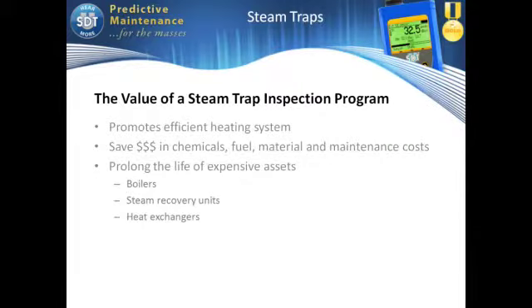You need to think about promoting an efficient heat system in the steam system. This is what it's about. We're trying to increase the efficiency of your heating system. I've been in situations where there have been so many problems with steam traps, so much air, so much condensate in the system, that they've not been able to achieve a certain temperature. Without this temperature, in a food industry case, they were unable to cook the product properly, or the cooking time was extended. The transit time through the oven had to be slowed down because they couldn't reach the temperature. In a pharmaceutical plant, they couldn't achieve temperature inside an autoclave with their steam system to trigger a chemical process.